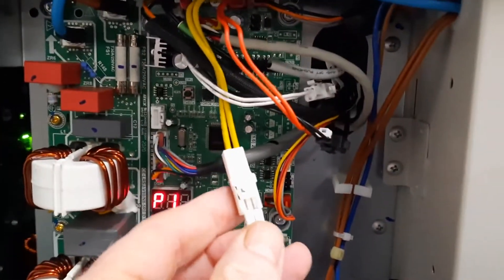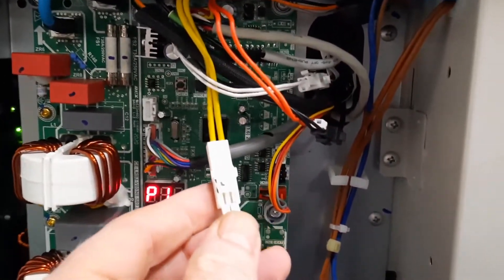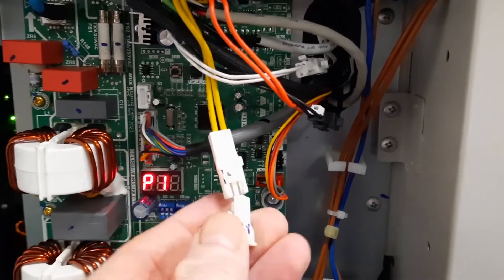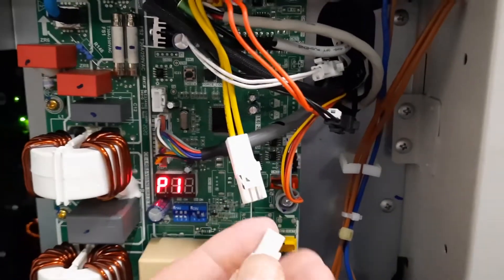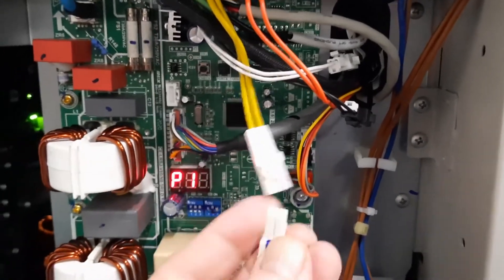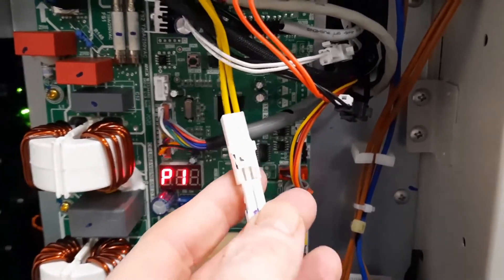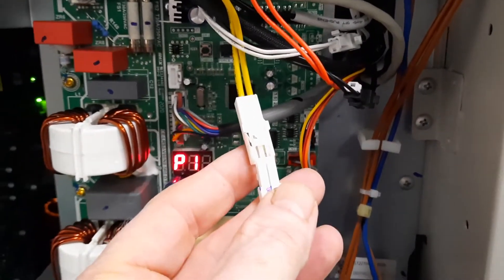And this jumper, I guess in the bad old days, would have had an HP switch on it. So all it means is this has come unplugged, plug it back in, fault code disappears.